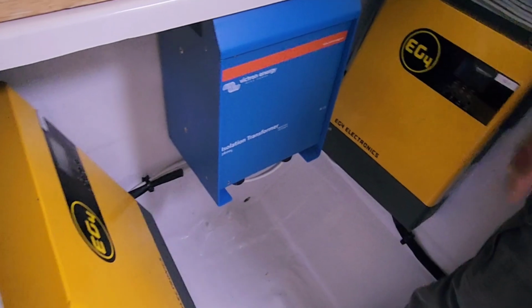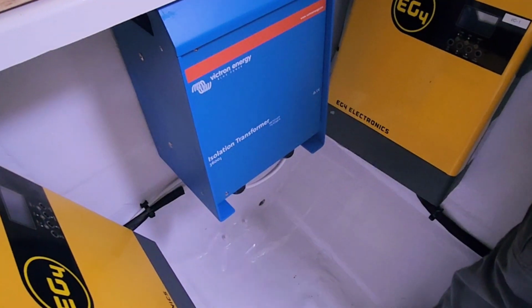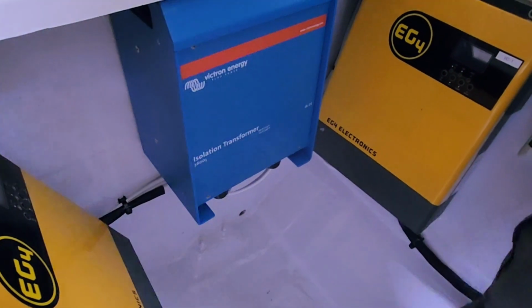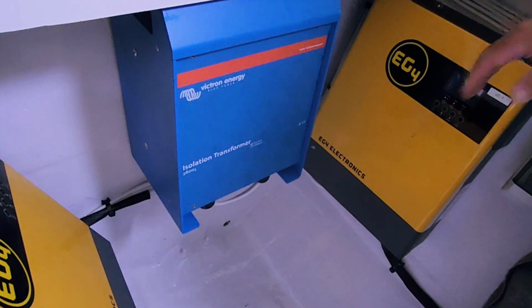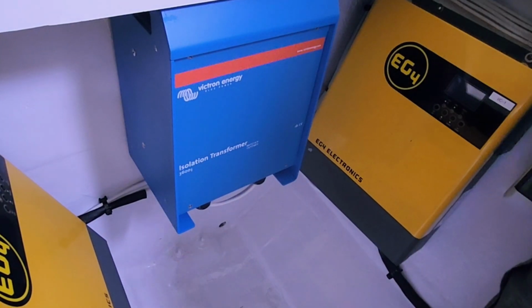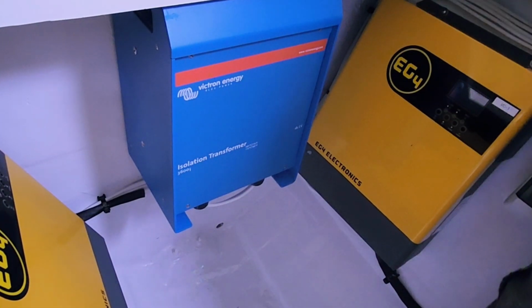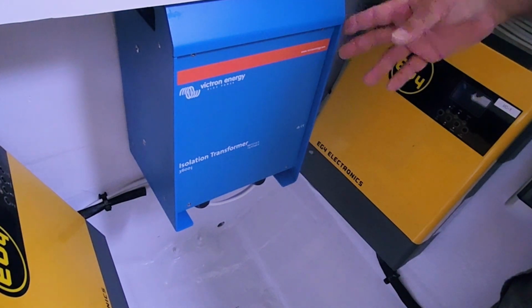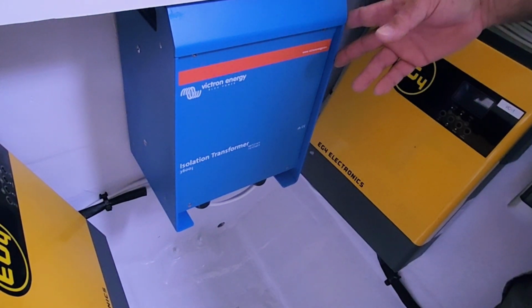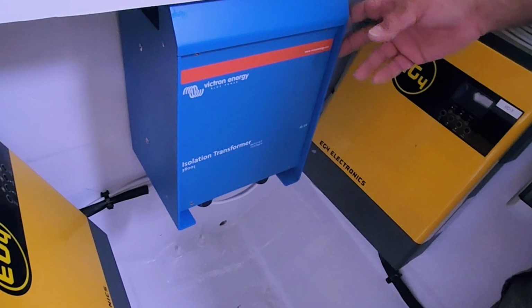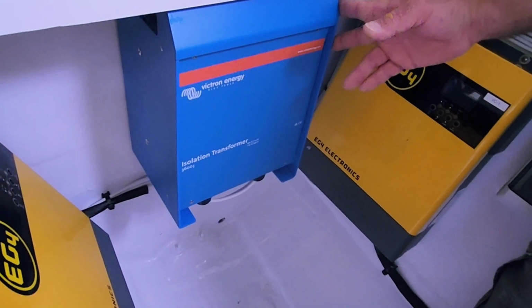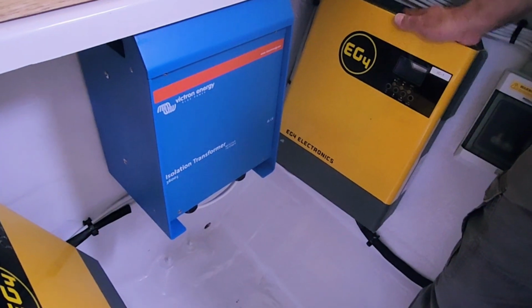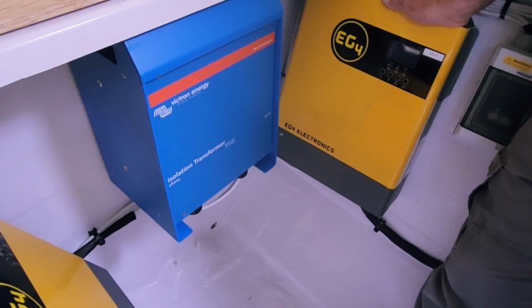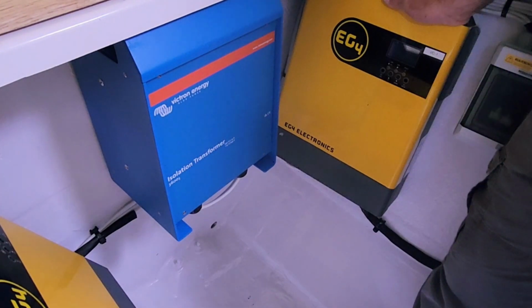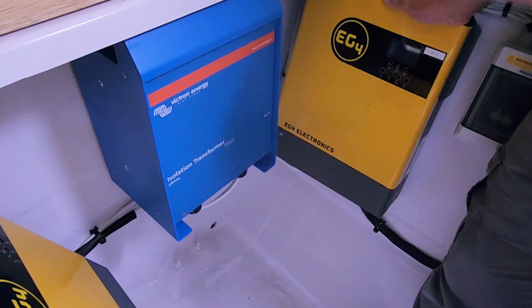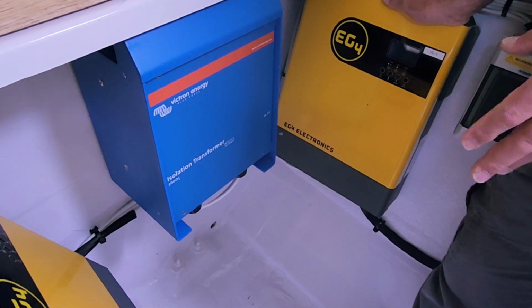This isolation transformer is hooked directly to our shore power plug. So when we do get power from the docks, it's going to go to this isolation transformer and be completely disconnected from the rest of the boat. This isolation transformer creates its own ground, creates its own neutral, and sends the one leg of 30 amp power over to one of the inverter chargers. I don't have it hooked up to both. I can hook up to one or the other, but not both.